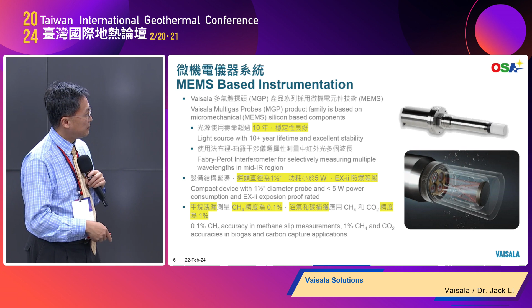Depending on your application, the accuracy of the CH4 measurement could be as low as 0.1% accurate. So if you're looking for methane slip, you will need to use this MGP 262 for lower range but better accuracy.